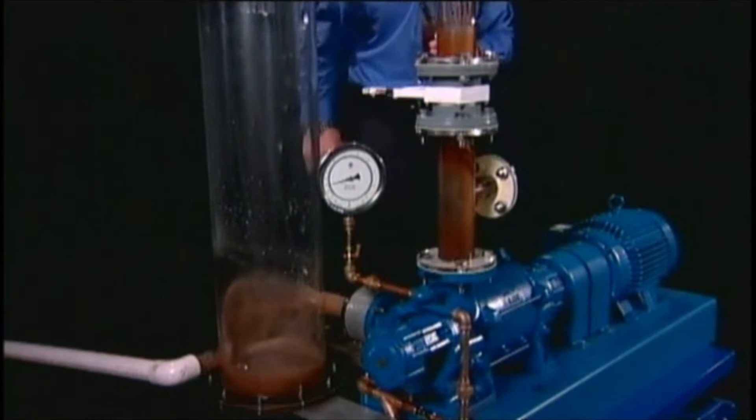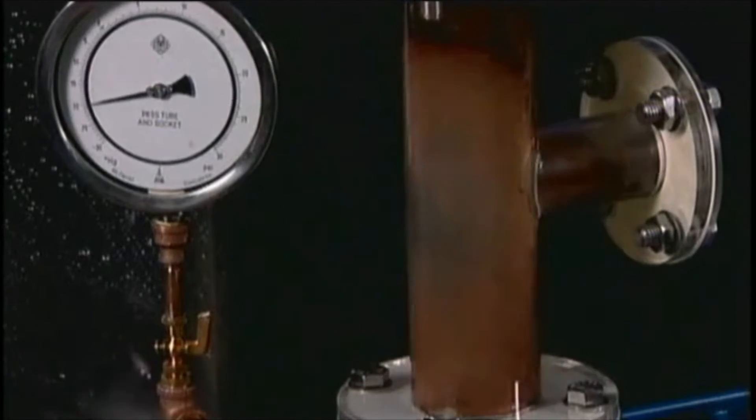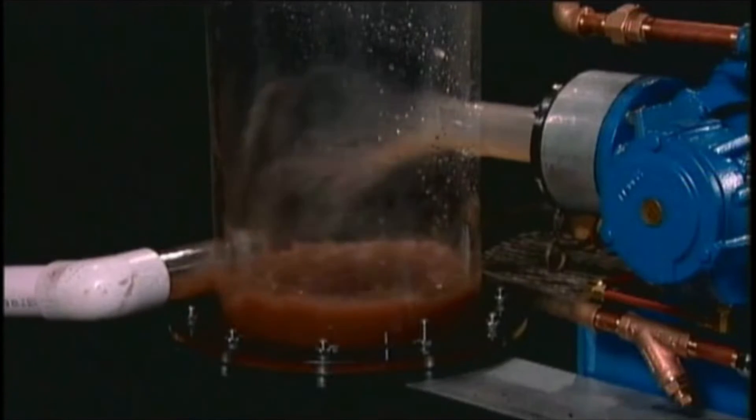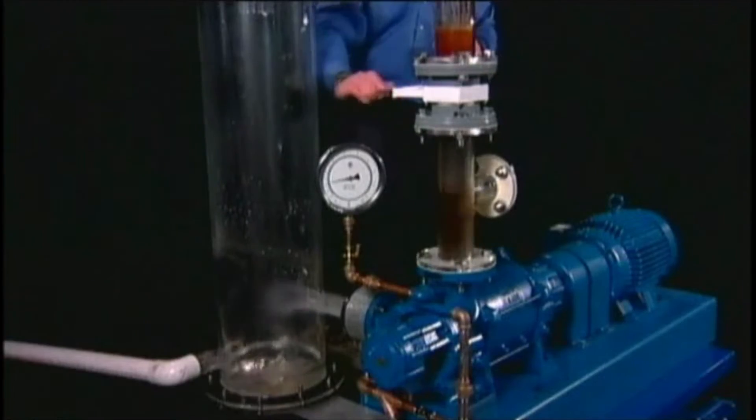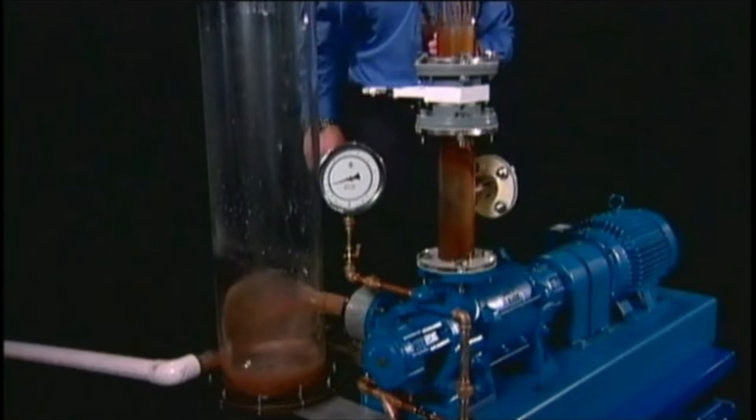Vacuum returns to normal instantly. The reason is our pump's design. With liberal clearances and no restricted passages, the pump lets granular and sticky matter pass. There is no internal buildup because the seal liquid flushes it right through and our rugged cross sections take the impact.